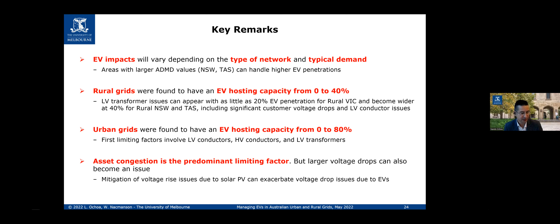We can do things with existing assets. For instance, our low voltage transformers have off-load tap changers in many cases, so if it comes to voltage issues, we could have better settings. We've been doing this for photovoltaics. The challenge with off-load tap changers, however, is that if you have photovoltaics, you were putting the taps down to get lower voltages, but now you want to bring the taps up for electric vehicles. You cannot do that simultaneously with an off-load tap changer because it's fixed.